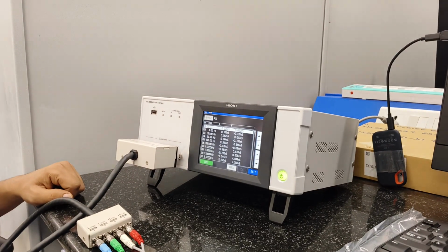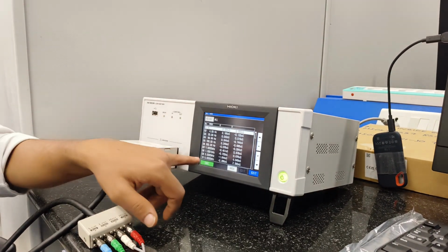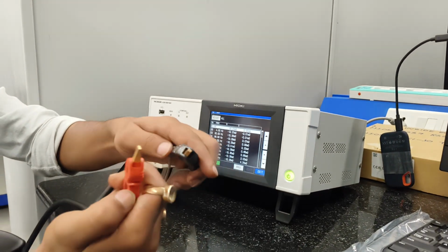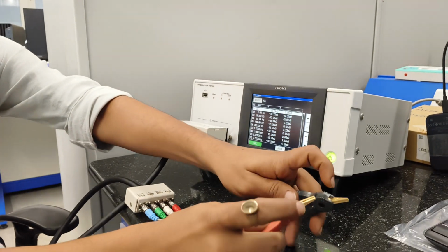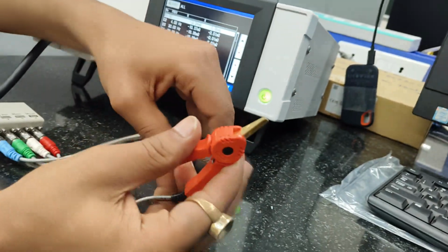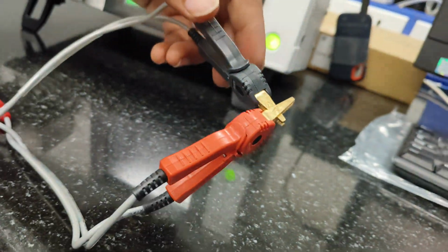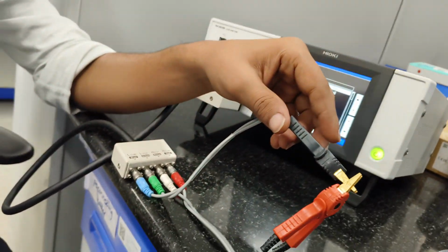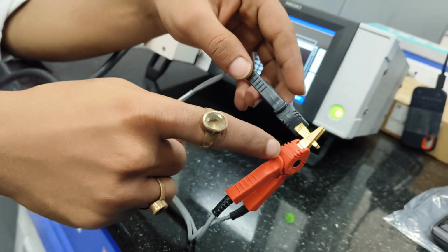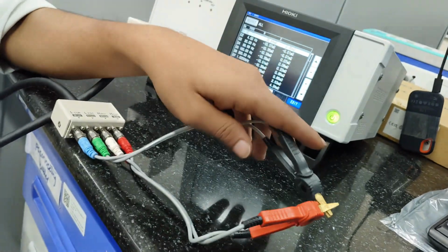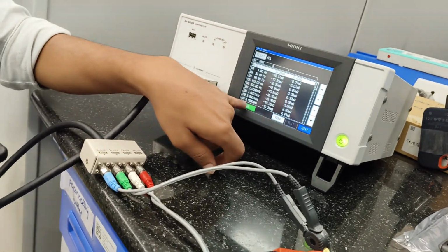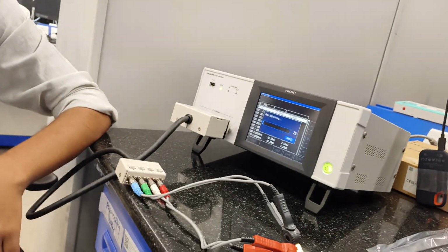So what we are doing is open compensation. Okay. And again shorting. Then I will short this one. Here the arrow is there. If you see, the arrow should be like this. This one is the 4-wire method. We are measuring with the 4-wire method. So these wires will get shorted like this, at 90 degrees. Okay. Now short circuit compensation is going on. Yes, sir.